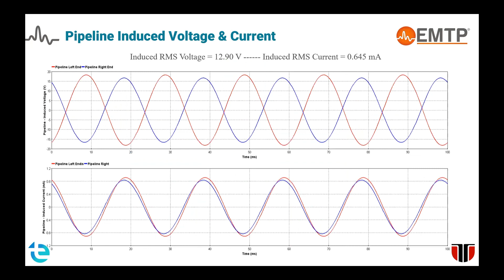If you want more detailed information on what happens along the distribution corridor and how the induced voltage varies along the pipeline, we have to divide the common distribution corridor into multiple subsections, usually based on the length between two power line towers. So in our case, we divided the 5-kilometer common distribution corridor into 10 subsections, each 500 meters.